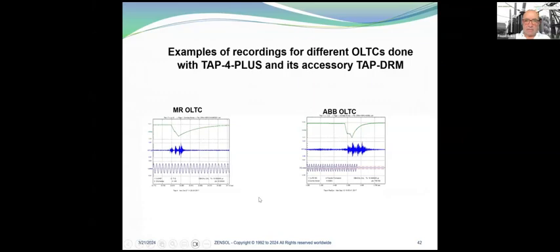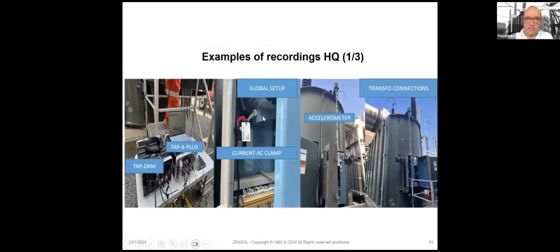So these are some examples of recordings for different OLTCs done by Tap 4+ and the accessory Tap DRM. Here are other examples. This is the global setup: Tap DRM, the accessory, the Tap 4+, the current clamp. In general, it's good to put a tag, so that the next year or in 2 years, you will come back exactly to the same location to avoid any wrong connections, because when you compare 2 signals it's important to compare them at exactly the same spot. The accelerometer is connected to the transformer.